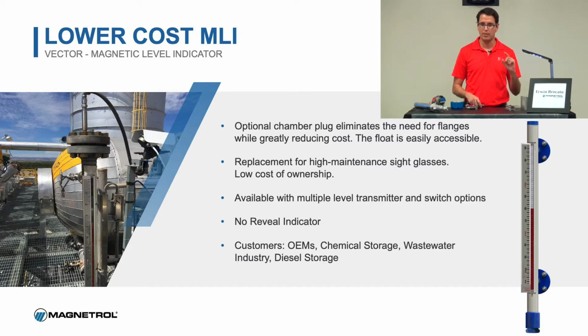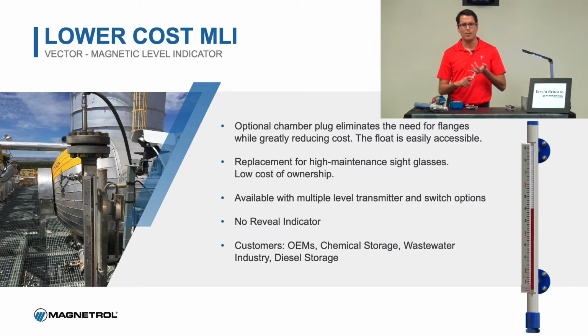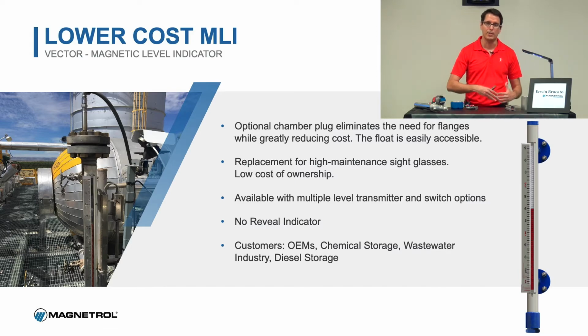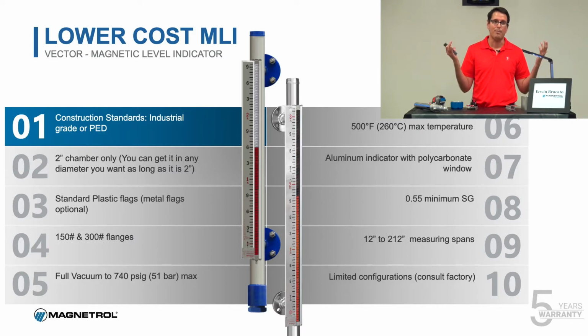The only thing I would mention, and I'll show a little bit on the camera later, is that we can also do level switches and level transmitters on these devices. This is perfect for a wastewater treatment facility. OEMs might buy some of these, or some kind of chemical storage where you just need a simple device to indicate level. You may not need a transmitter. You might just need a local indicator, and you don't want to deal with a sight glass, because if the sight glass breaks, you might have a spill, and you don't want to be replacing sight glasses. Or you probably can't even see the level. I'll show you another image after this that's pretty good. It shows you why we want one of these instead of a sight glass. Okay.